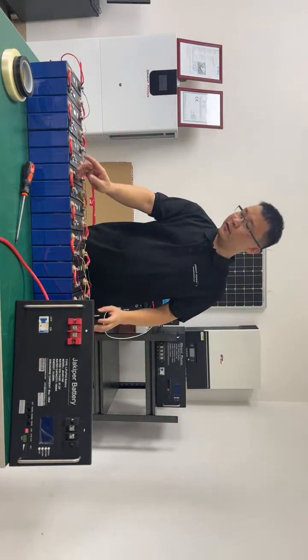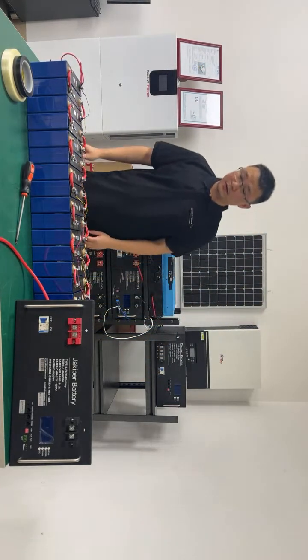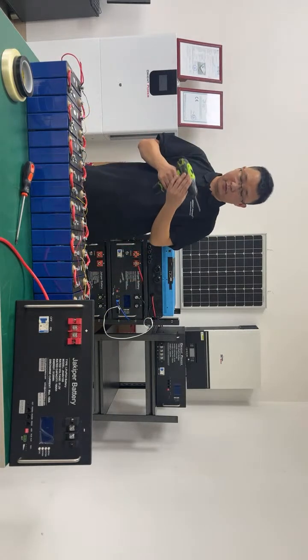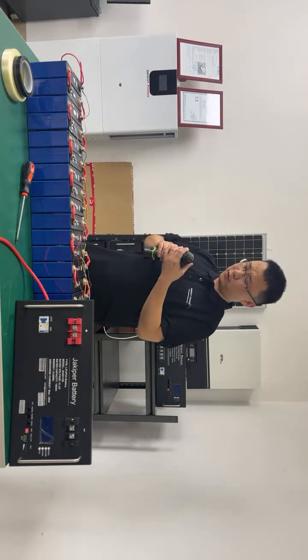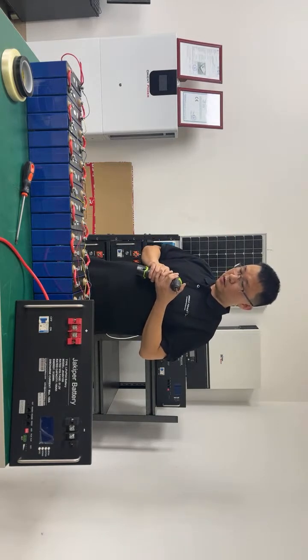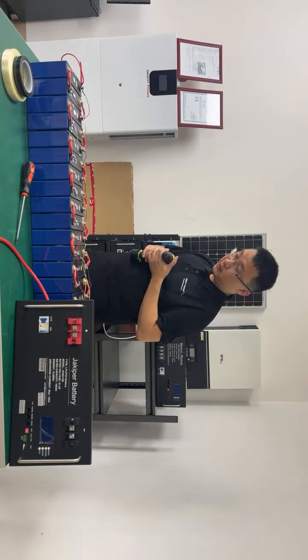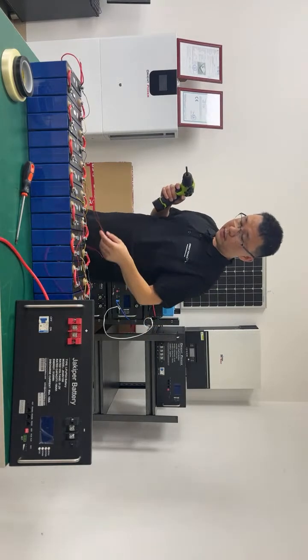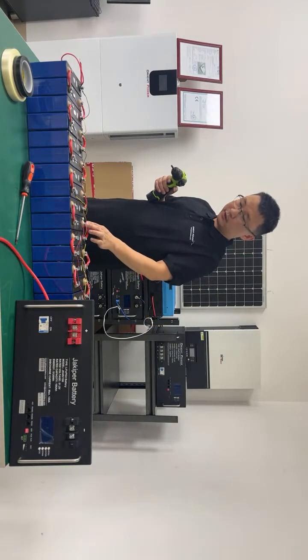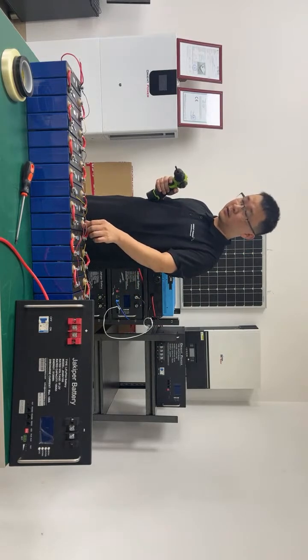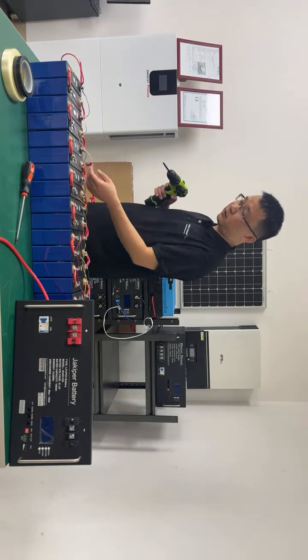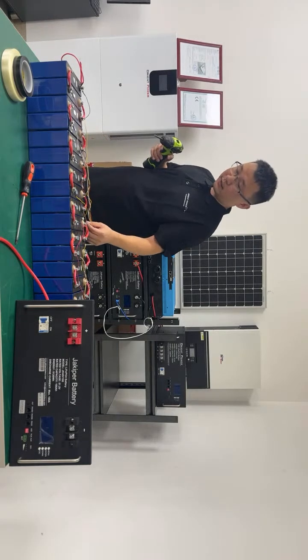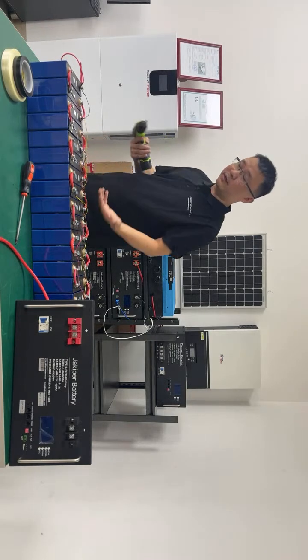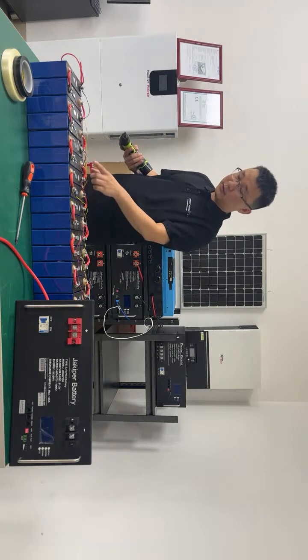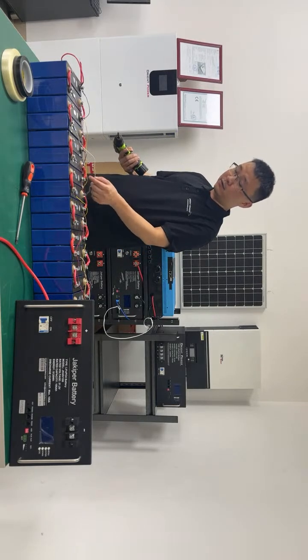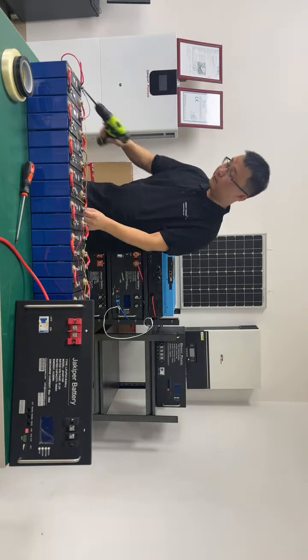For all these wires, when you tighten them, you can use the torque wrench, but here I just use this metal rigidity machine to get approximately proper torque. If you have the torque wrench, you can double check to make sure the connection is around 10 Newton meters, not much, not less. If you tighten too much, the thread may get damaged, and if you tighten too little, internal resistance will increase and you will have imbalance across the cells.